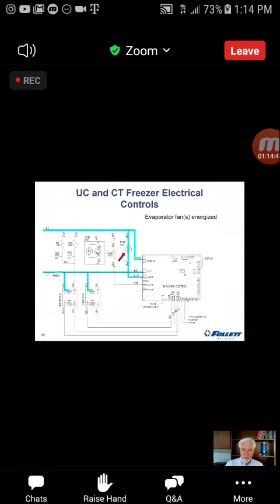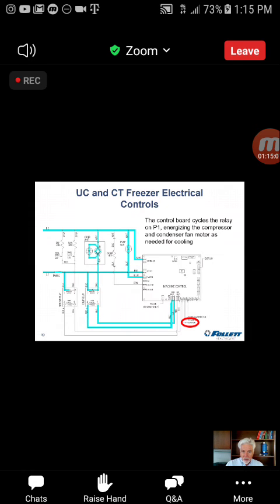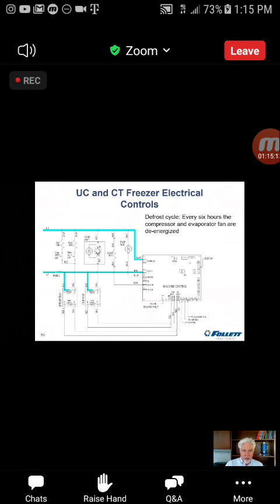So when we power up the unit, like the refrigerators, the fan motor is energized. On freezers, the evaporator fan motor runs constantly. The only time we shut it off is during the defrost cycle. The rest of the time, it's running always. Like before, we're cycling the temperature on the P1 control probe based on temperature there. Same as before, we're just closing the contacts of that relay.